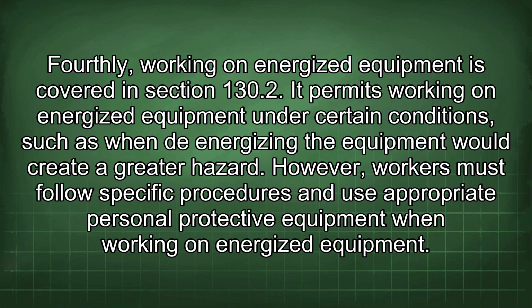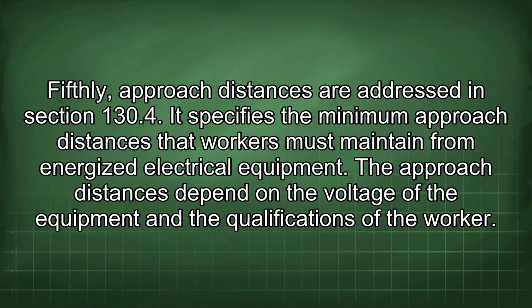It permits working on energized equipment under certain conditions, such as when de-energizing the equipment would create a greater hazard. However, workers must follow specific procedures and use appropriate personal protective equipment when working on energized equipment. Fifthly, approach distances are addressed in Section 130.4. It specifies the minimum approach distances that workers must maintain from energized electrical equipment. The approach distances depend on the voltage of the equipment and the qualifications of the worker.